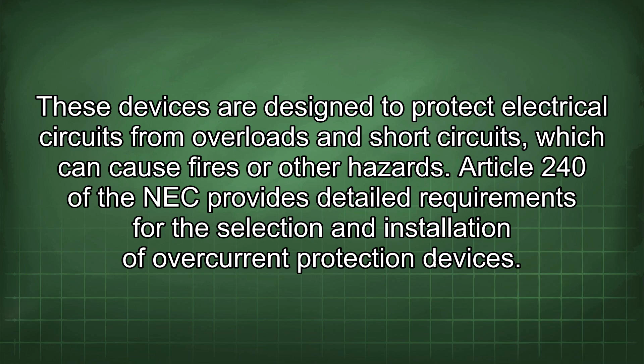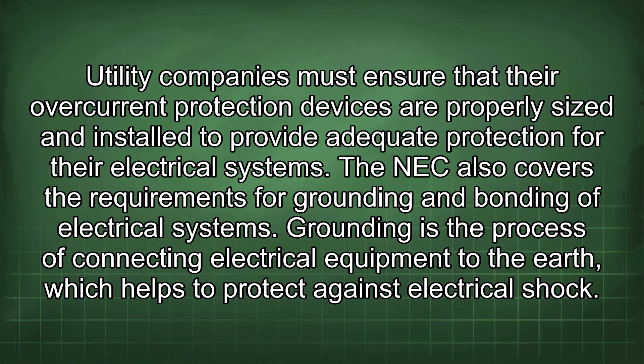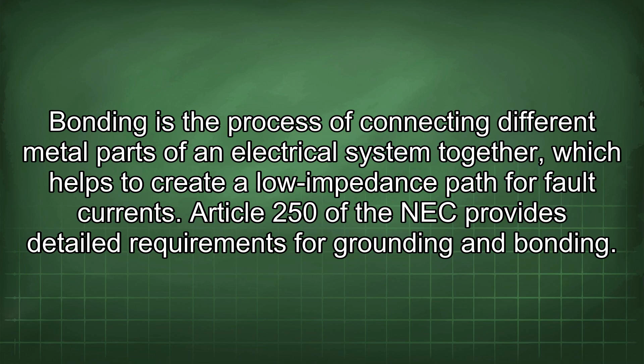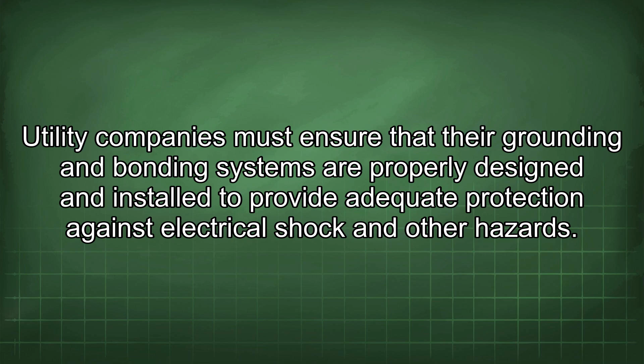The NEC also covers the requirements for grounding and bonding of electrical systems. Grounding is the process of connecting electrical equipment to the earth, which helps to protect against electrical shock. Bonding is the process of connecting different metal parts of an electrical system together, which helps to create a low impedance path for fault currents. Article 250 of the NEC provides detailed requirements for grounding and bonding. Utility companies must ensure that their grounding and bonding systems are properly designed and installed to provide adequate protection against electrical shock and other hazards.